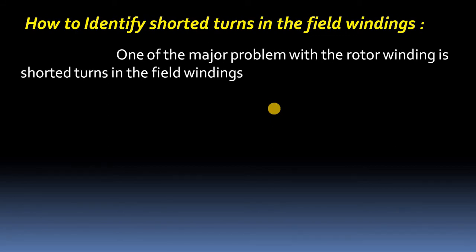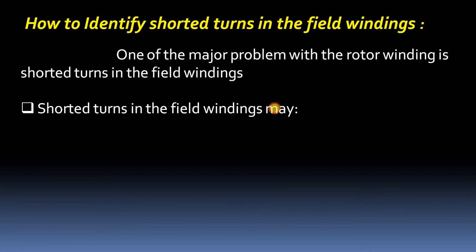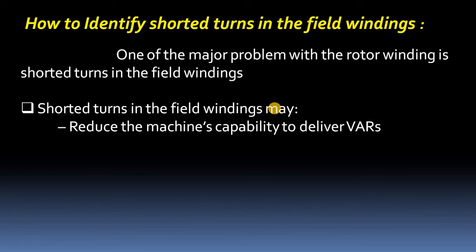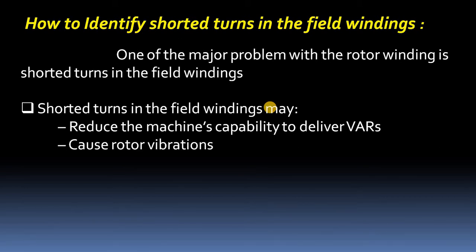Shorted turns in the field winding may reduce the machine's capability to deliver VARs. If the field pole has shorted turns, that will reduce the net flux generated by the field poles, thereby reducing the machine's capacity to deliver rated reactive power. Shorted turns also cause rotor vibrations.